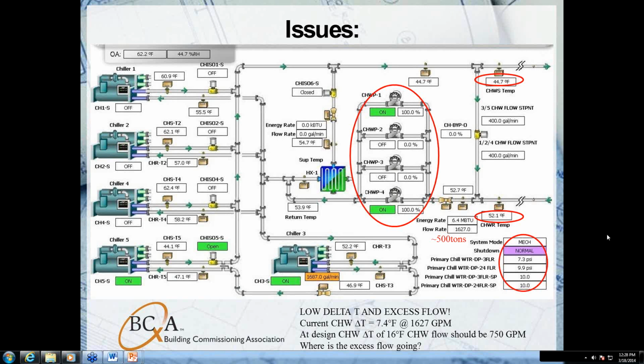So the way it was valved and piped was if you ran chiller 3 and 5, they were running together, and they would get enabled together. So when you turn them on, it was turning them on basically together. And basically the chilled water would come back to chiller 3 first. So it would take basically the load, it would get the set point, it would then go through chiller 5, and chiller 5 basically said, I have no load, so I'm going to shut down. And after a couple times of cycling on, cycling off, cycling on, cycling off, it would just get into its own lockout, and it would just say, I'm not going to run anymore. So that was sort of the problem of abandoning it.